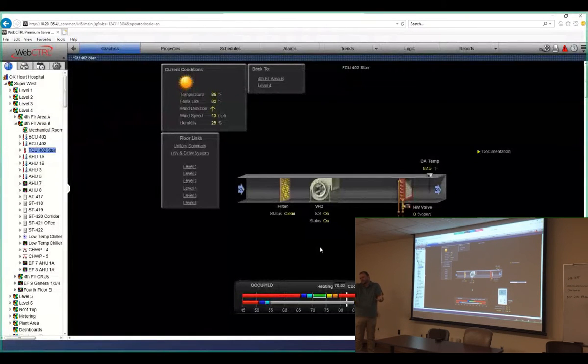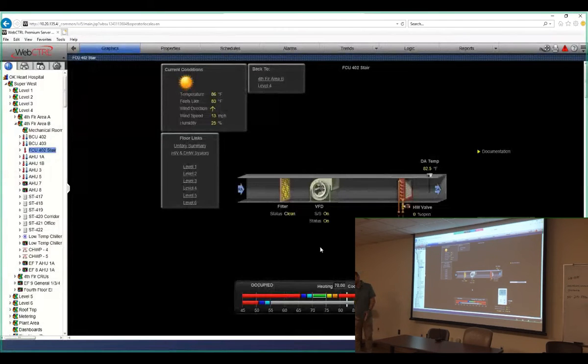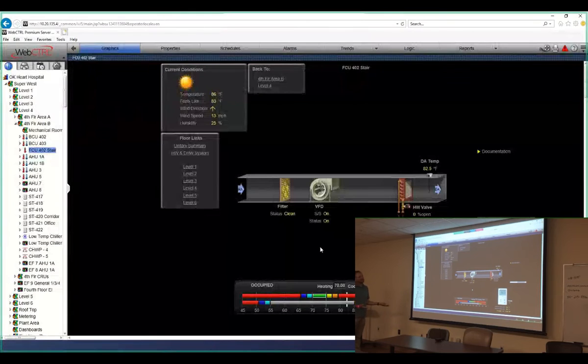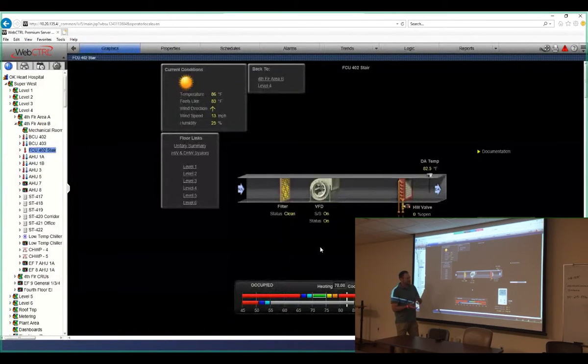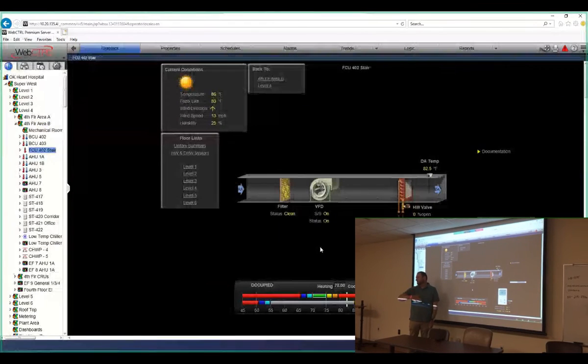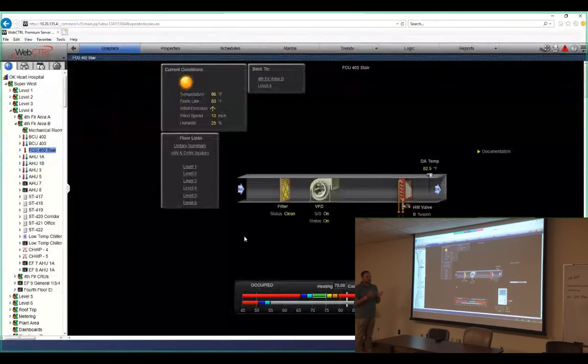That's all you're really looking for, is that most people aren't traveling up and down those stairwells. No, that keeps them plenty warm enough. Yeah, keeps it from freezing. Well, if you get it any warmer than that, you use the stairs, you're sweating before you get there. Yeah, right. So there's 4 that I know of. Yeah, I believe there's 4. They just heat and warm the space, so pretty simple. Again, these things, we're monitoring the filter status, start-stop status, discharge temperature. If we drop below the heating set point, we're going to warm it up with the valve, and that's it. And the fan runs 24/7. So those are the 4 locations for the fan coil units.